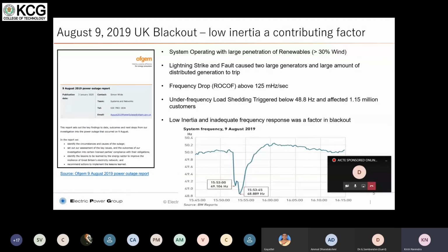That was suddenly off, and at that time the distributed energy generation or renewable generation was around 35%, around 700 megawatts of wind and solar were there, and there was no inertia support from them for the reason I explained: because of their electronically made devices, they are not allowed to put their kinetic energy back into the system. In the case of wind, you will have zero inertia support to the grid. Now, because of that, the rate of change of frequency goes down.